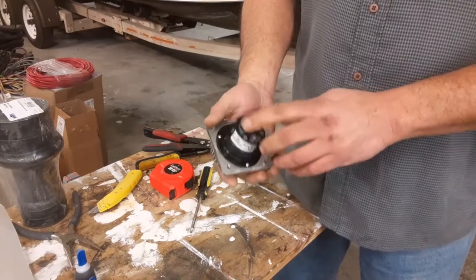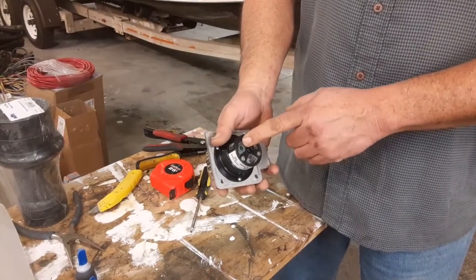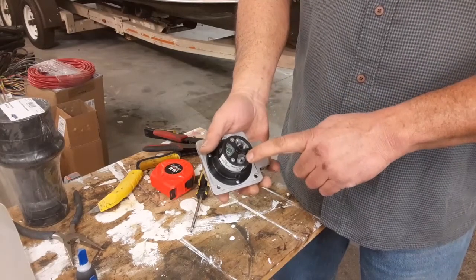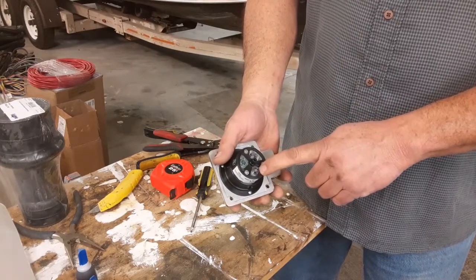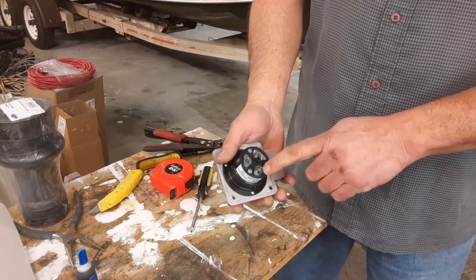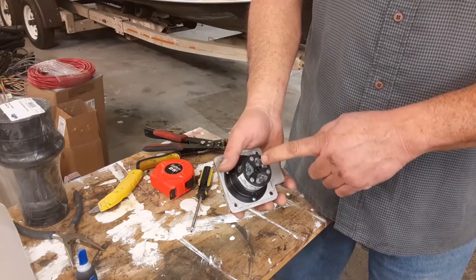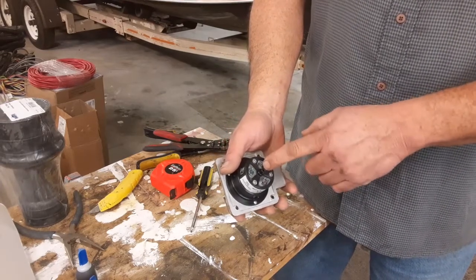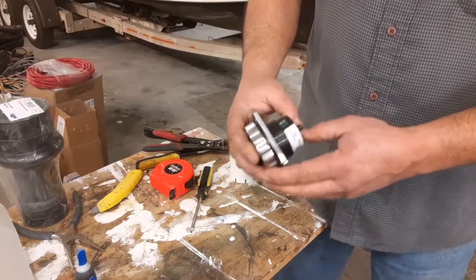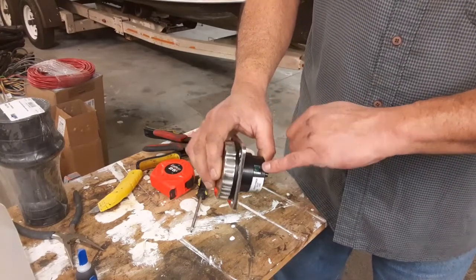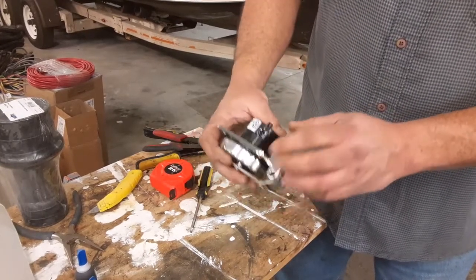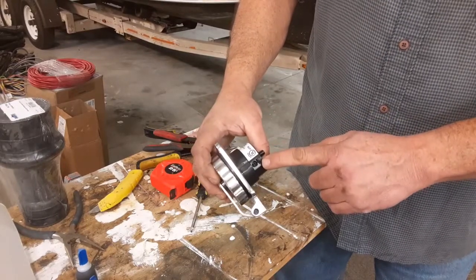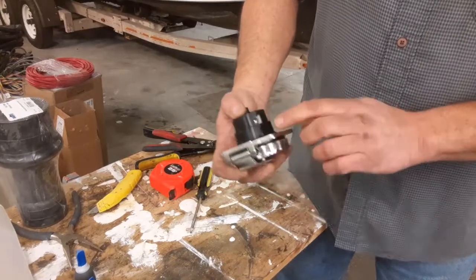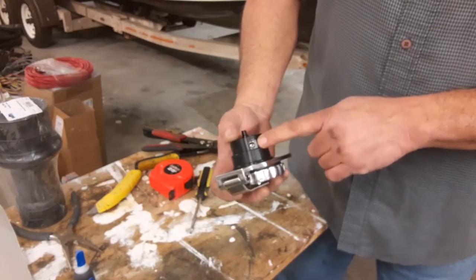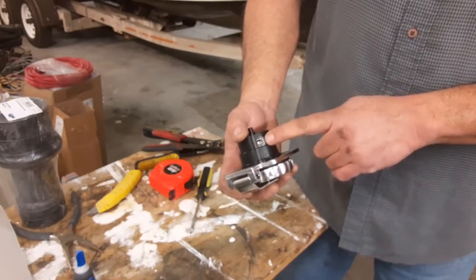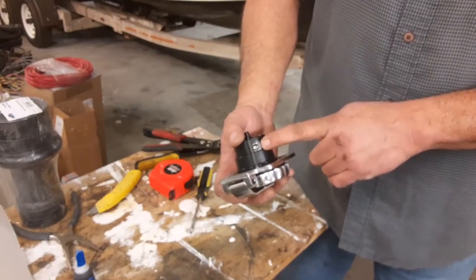On the back side of it there are three connections: a ground, colored green; the power supply, 120 volts, with a black ring around it, you may not be able to see that; and the neutral, or white wire, which doesn't have anything around it. You can also identify these by the screw colors: green for ground, black for power, and a stainless-looking bright color for neutral.